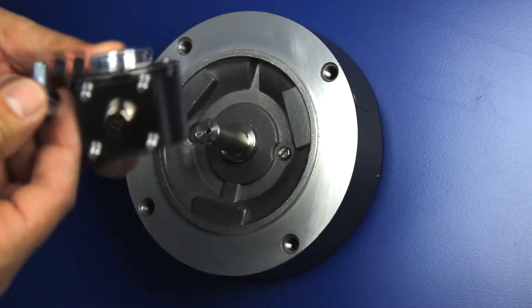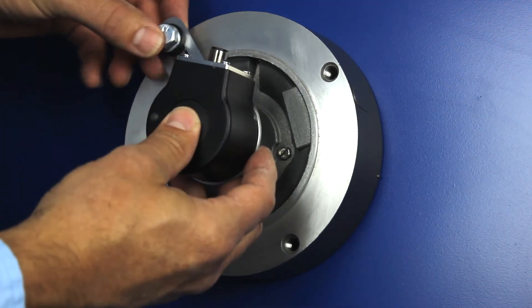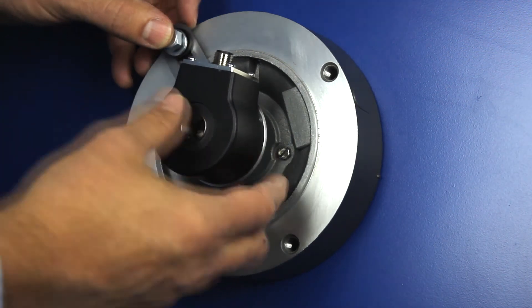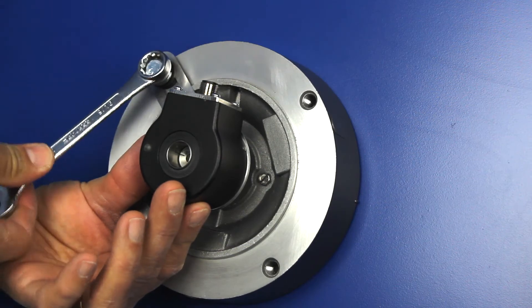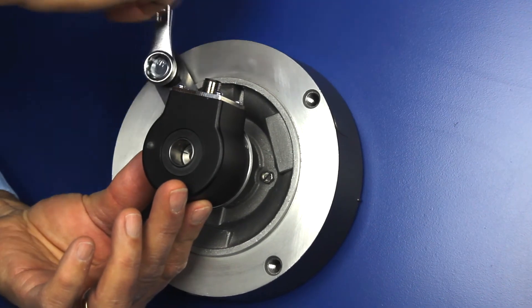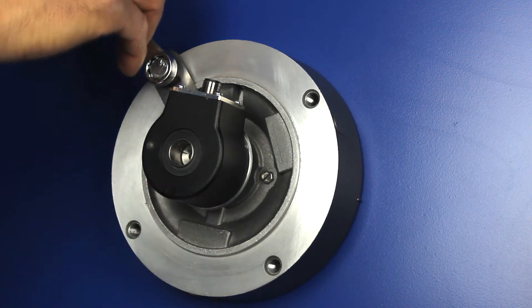Assemble the washers and mounting bolt in the flex mount slot and position the encoder radially on the motor shaft. Tighten the mounting bolt securely. Do not strike or apply excessive axial or radial force when installing, otherwise you can damage the bearings.